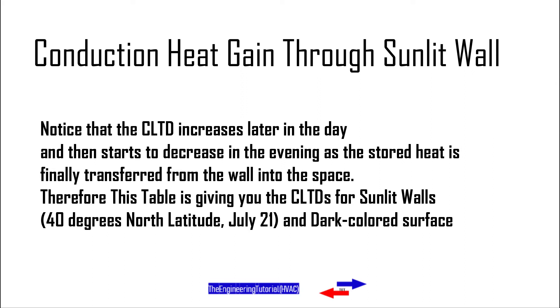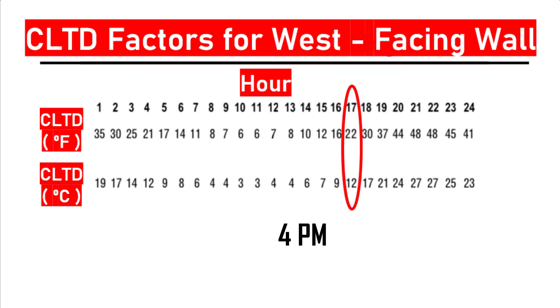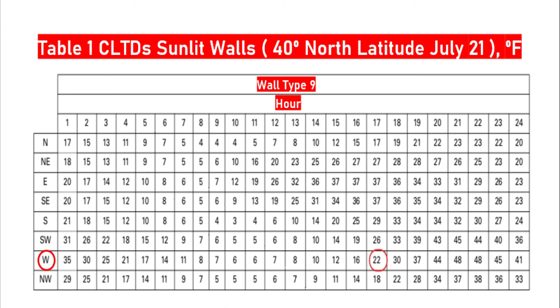More tables for various wall and roof types, as well as correction factors for applications that differ from these assumptions, can be found in the 1997 ASHRAE Handbook of Fundamentals and ASHRAE's Cooling and Heating Load Calculation Principles manual. The wall in our example is classified as wall type 9, at 4pm — hour 17 in this table. The CLTD for a west-facing wall of this type is 22 degrees Fahrenheit. This means that even though the actual dry bulb temperature difference is only 17 degrees (95°F minus 78°F), the sun shining on the outer surface increases the effective temperature difference to a CLTD of 22 degrees Fahrenheit.